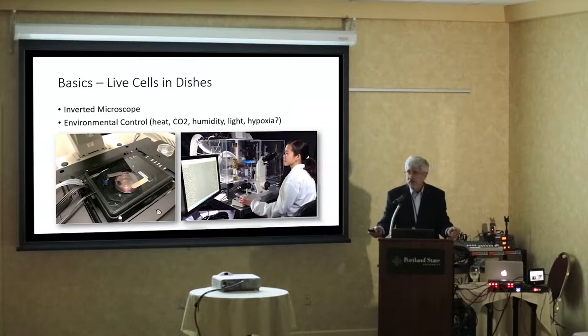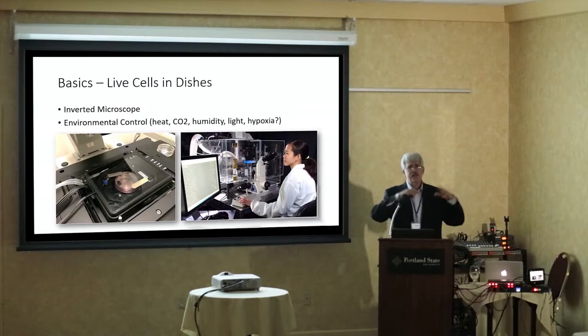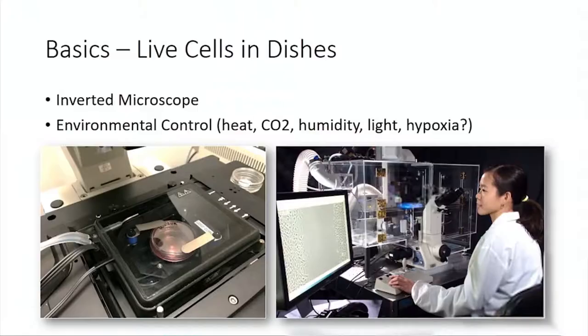Environmental controls come in basically two flavors: a stage-top control, and one that encloses the entire microscope. The basic things we're looking for are heat control, CO2 control, humidity, and light. Occasionally we have people doing hypoxic experiments where you're lowering oxygen levels, and for that I really need the enclosed one which can push out oxygen with nitrogen. Depending on what you need to do, you might use one or the other.